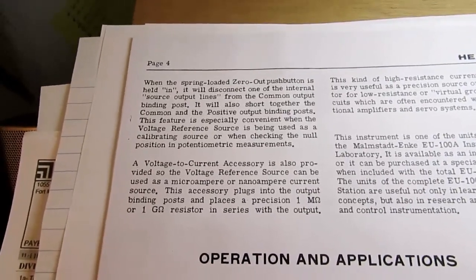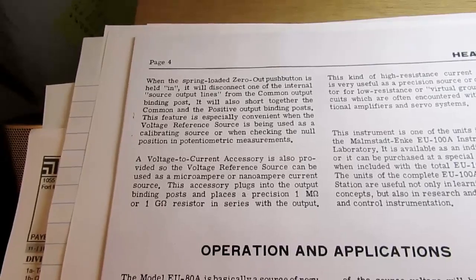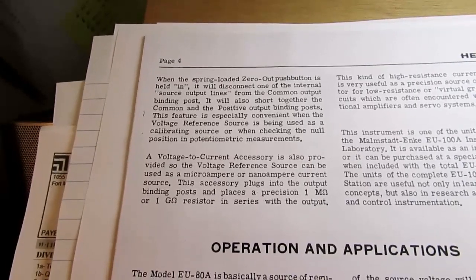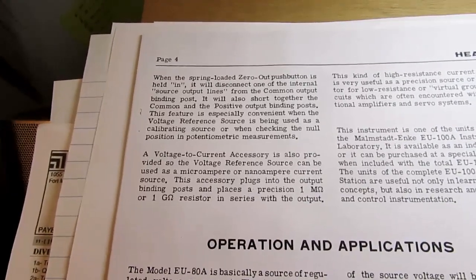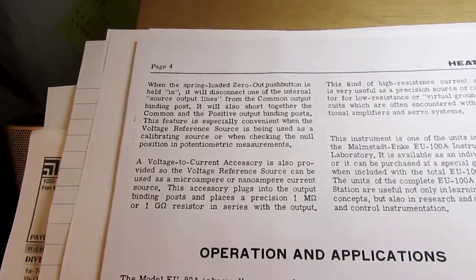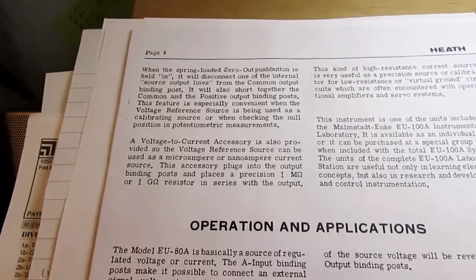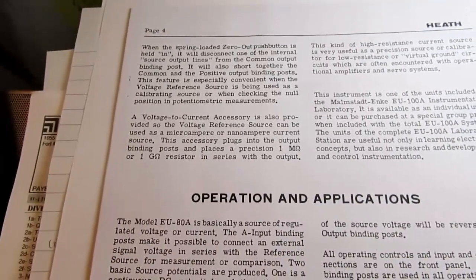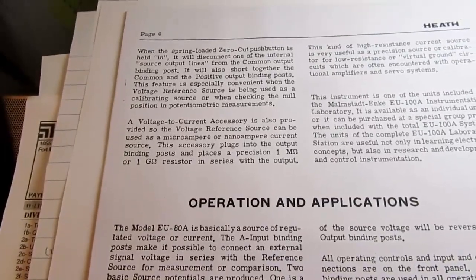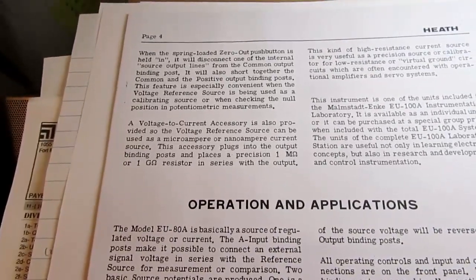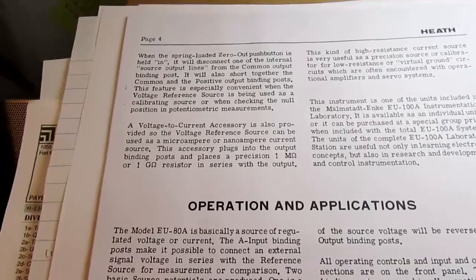This feature is especially convenient when the voltage reference source is being used as a calibrating source, or when checking the null position of potentiometric measurements. A voltage to current accessory is also provided so the voltage reference source can be used as a microamp or nanoampere current source.